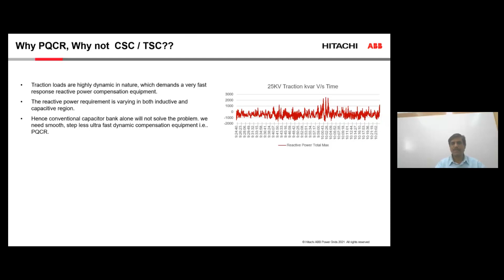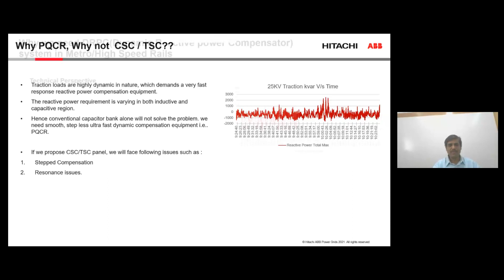So if we do have a capacitor-based solution, what we call contactor switched capacitor or thyristor switched capacitor, it can give step compensation, and can also have resonance issues. Therefore, we say that the PQCR is probably the best suited for high-speed rail. From a technical perspective, we see what's happening in a TSS, the traction substation. We are looking at a highly dynamic load. It starts from a few kVAs and goes up to several MVA within a few minutes, sometimes within seconds. So we can't rely on a fixed capacitor or a fixed compensation to solve the power quality problems there.